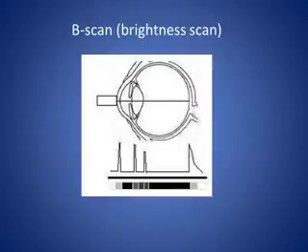The largest amplitude gives rise to a spot with the greatest brightness, here shown almost white. The smallest amplitude gives rise to a spot which is almost black, and intermediate amplitudes give various shades of grey. The area that does not give rise to any spike, for example in the eye, the aqueous and the vitreous, will appear black. The corneal spike and the retinal spike in this image have the biggest amplitude and therefore appear nearly white.